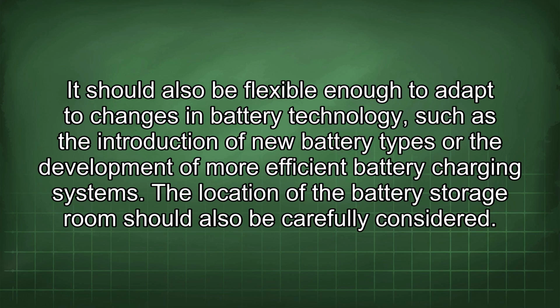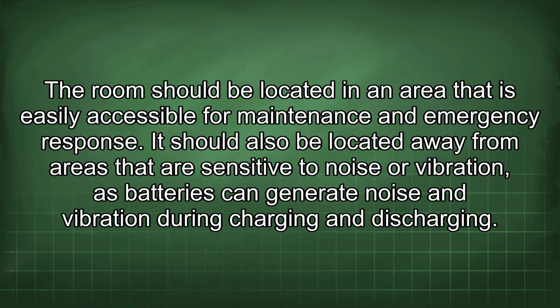The location of the battery storage room should also be carefully considered. The room should be located in an area that is easily accessible for maintenance and emergency response. It should also be located away from areas that are sensitive to noise or vibration, as batteries can generate noise and vibration during charging and discharging.